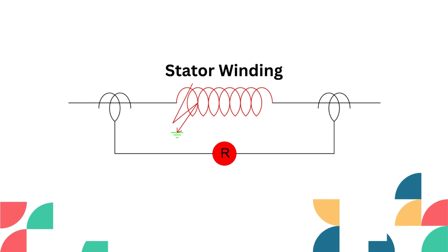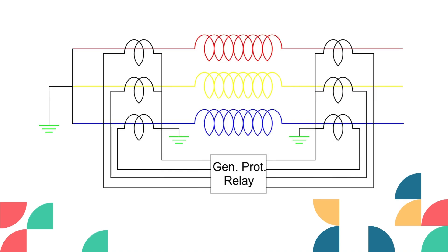To understand more deeply, we need to understand the connections inside the generator. To measure the incoming and outgoing current of each winding, CTs are connected to both the neutral side and the outgoing terminal side of each phase of the stator winding. For a 200-megawatt generator, approximately 9,000 to 10,000 amperes flows through each phase. However, the relay is not designed to handle these high currents. These CTs will drop the value and send the current to the generator protection relay.